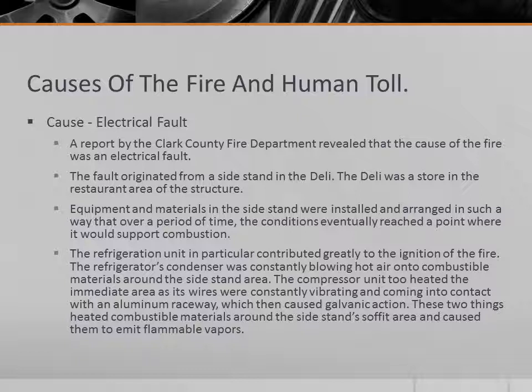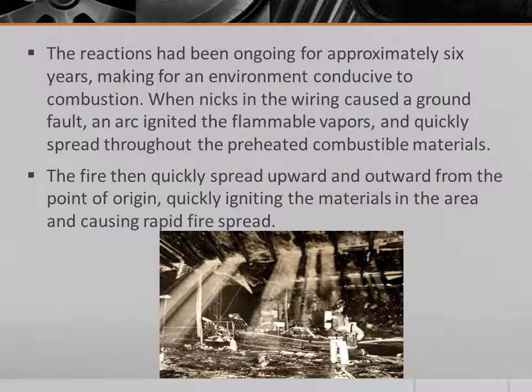These two things heated combustible materials around the side stand soffit area and caused them to emit flammable vapors. The reactions had been ongoing for approximately 6 years, making for an environment conducive to combustion. When nicks in the wiring caused a ground fault, an arc ignited the flammable vapors and quickly spread throughout the preheated combustible materials. The fire then quickly spread upward and outward from the point of origin, quickly igniting the materials in the area and causing rapid fire spread.